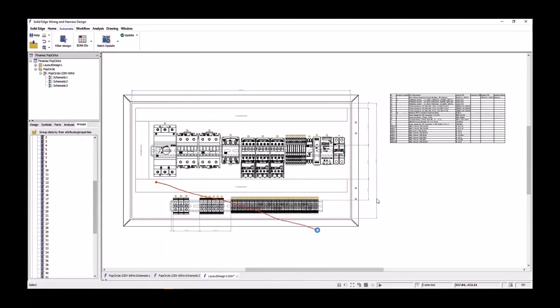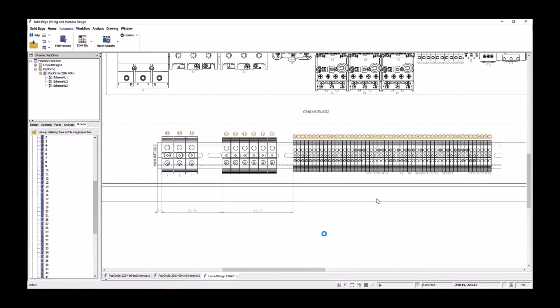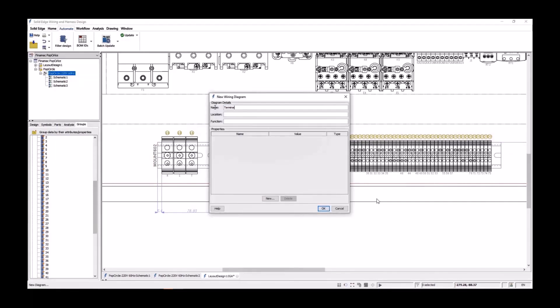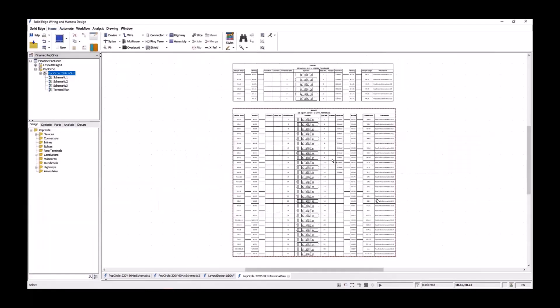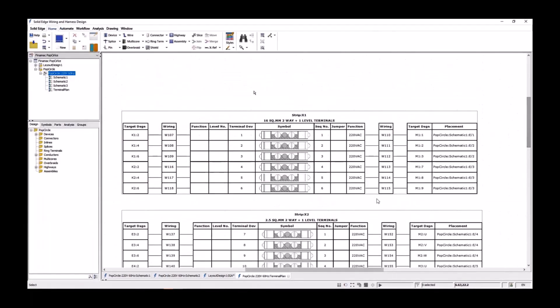The final deliverable required is a terminal plan to assist in the assembly and wiring of the terminal strips. This is easily achieved by creating a new diagram in the project design folder. The terminal plan tables are automatically generated, documenting the terminal blocks along with their specific symbol, physical sequencing, the strip and details of where the wires terminate at both ends of each block. Single and multi-level terminal blocks can be modeled as required. As the table content including connectivity is reused from the schematic design, any changes made downstream will automatically be reflected, providing accurate and up-to-date information.